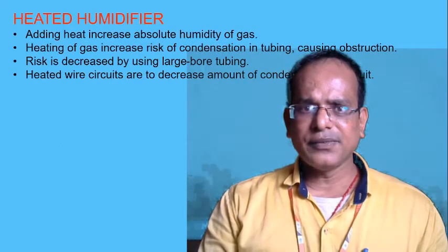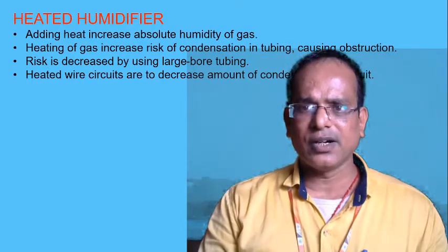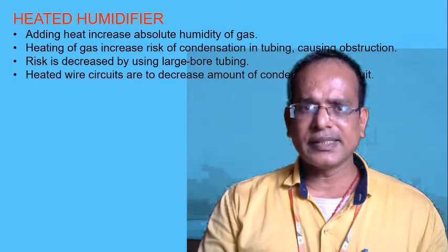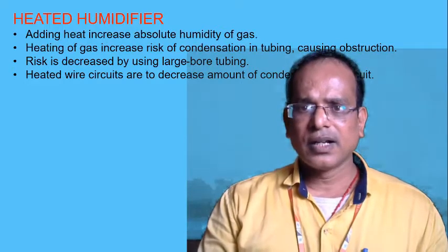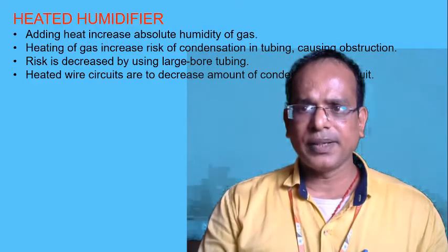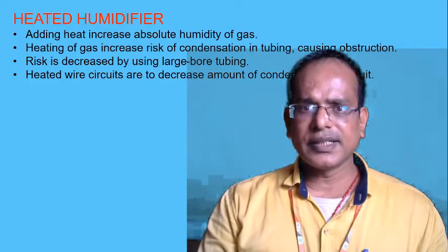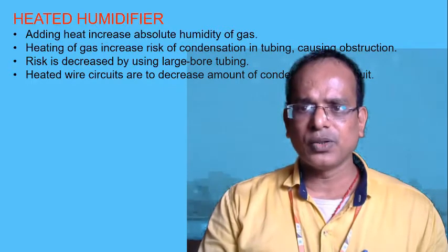Heated humidifier: adding heat increases the absolute humidity of gas. Heating gases increases the risk of condensation in tubing, causing obstruction. Risk is decreased by using large bore tubing, or a heated wire circuit, to decrease the amount of condensation in the circuit.